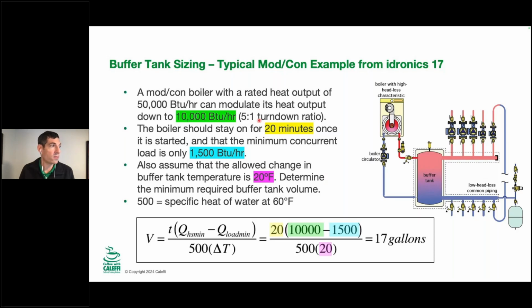We need to know these 4 variables. So let's say that we have a 50,000 BTU boiler and it can turn down at a 5-to-1 turn down ratio. That means that the smallest amount of energy that it can sustain to come out of the mod con is 10,000 BTUs per hour. This is an important one. How long do we want the buffer tank to buffer, how long do we want the battery to last when we charge it up?